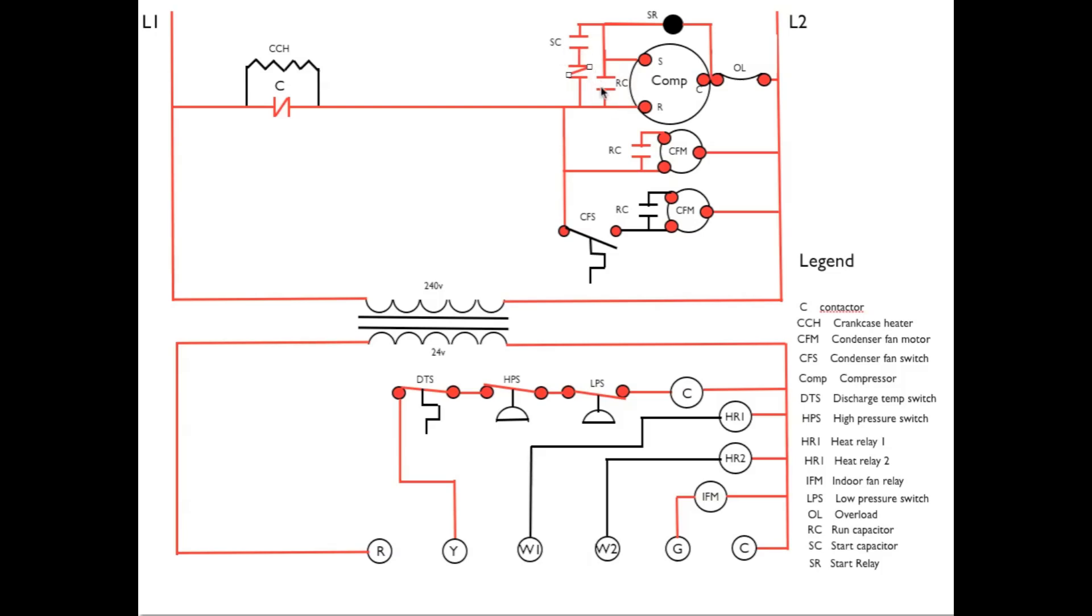This will be, if this was 40 microfarads, this may be 200 to 400 microfarads. So, this will give power up through the start capacitor, down through here, and over to the start winding. So it's going to give the start winding a big boost.